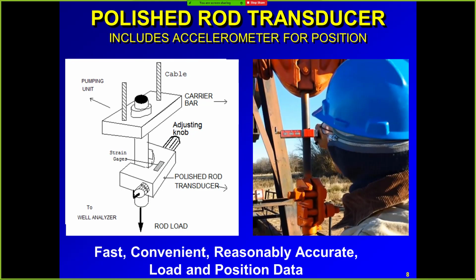Now this is an example of the polish rod transducer, the wireless one, that this person has attached to the well. And you can see that there's three buttons here, and there's an on button, and we can use these buttons to turn the PRT on, and the TAM software knows that the wireless system's on, and then it communicates back and forth, and you can adjust the tightness with a handle, and the lights will flash green when it's properly tightened.